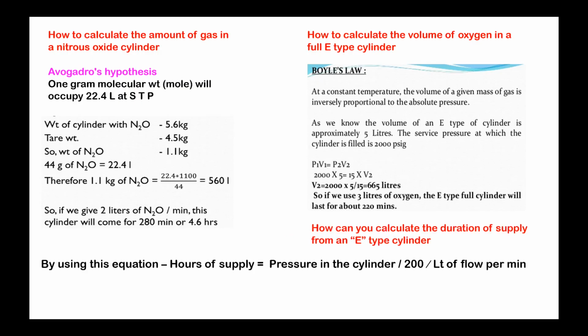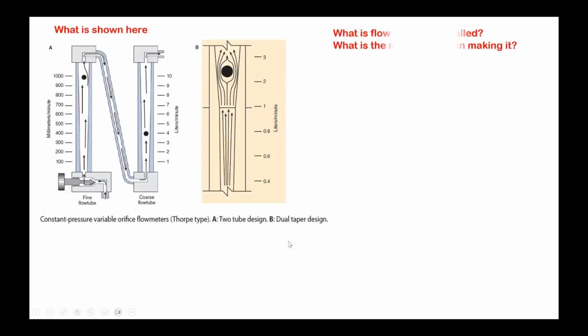Okay? But based on the duration, you can also calculate like this. The hours of supply is equal to the pressure in the cylinder divided by 200, divided by the liters of flow per minute. For example, if the cylinder pressure is 1000 and the flow rate is 2 liters per minute, then the duration you will have is only 2.5 hours. So these are all the flow meters.